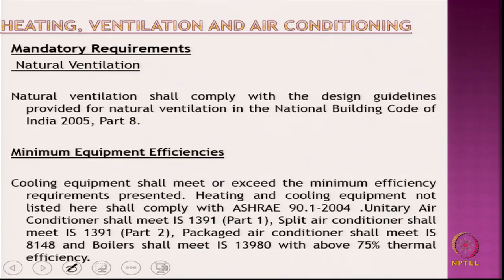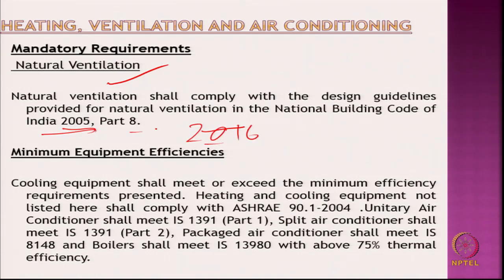But there are certain mandatory requirements. For example, natural ventilation shall be the minimum that is required for hygienic requirements. That is given as per, well, this is now changed to the 2016 National Building Code. This gives you the minimum hygienic ventilation requirement. So, it should be according to that, and then cooling equipment should meet the minimum efficiency requirement prescribed. The test equipment shall comply with the BIS guidelines, etc. So, a split air conditioner shall meet IS 1391, a packaged air conditioner should meet IS 8148, and so on.